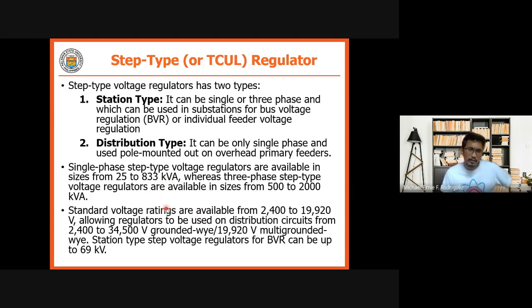The voltage ratings range from 2,400 volts up to 19,920 volts, allowing the use of regulators on circuits from 2,400/4,160 up to 34,500 volts grounded Y by 19,920 volts multi-grounded Y. The station type can be used for bus voltage regulation up to 69 kilovolts.